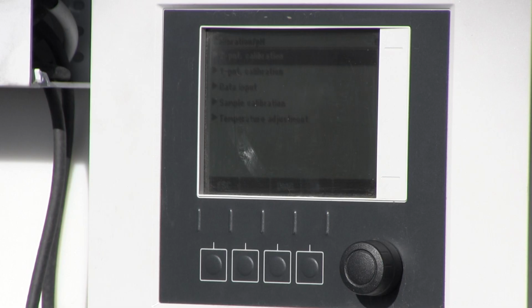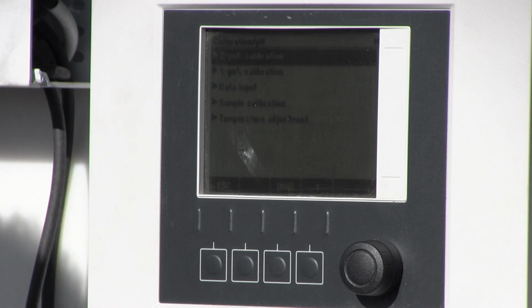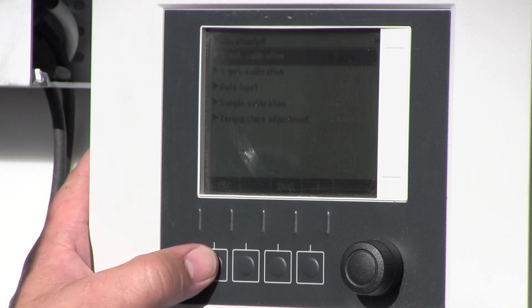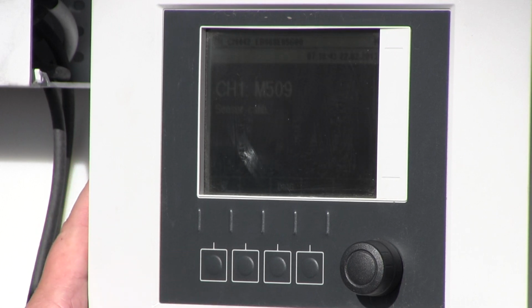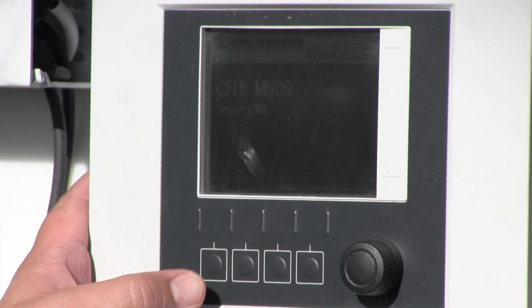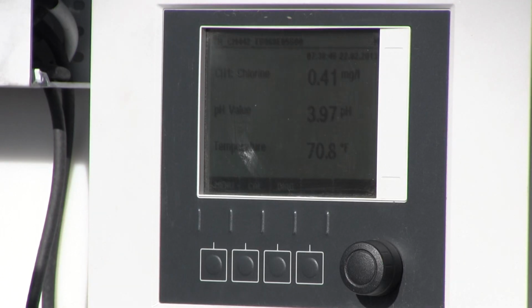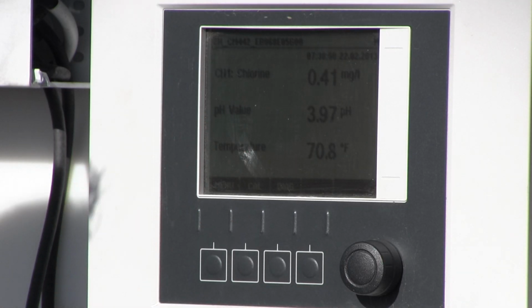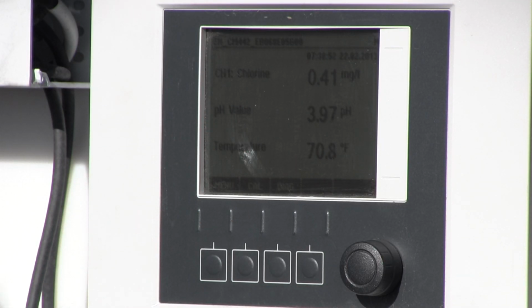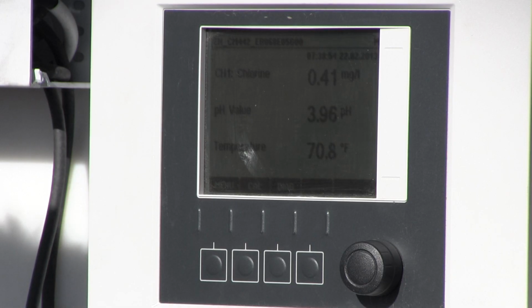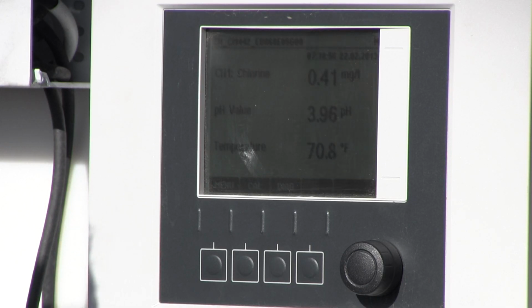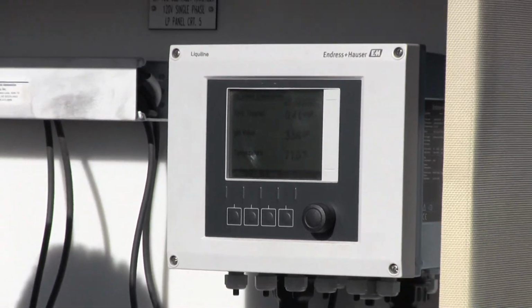Hit OK again. At this point, before I take it out of the 4 buffer, I like to do something to cross-check the plausibility of the calibration. I'm going to hit the escape key, simply going to hold it down, and I see that my pH electrode is reading a value of 3.97 in a 4 buffer. That's close enough for a pH electrode that's probably several months old. I'll now dump the 4 buffer, start a little bit of water through to rinse it out.